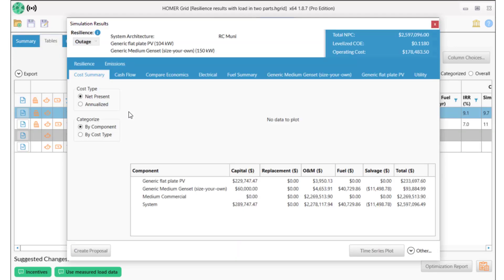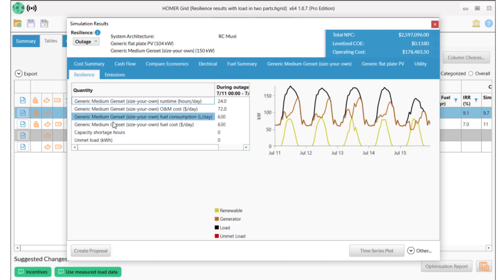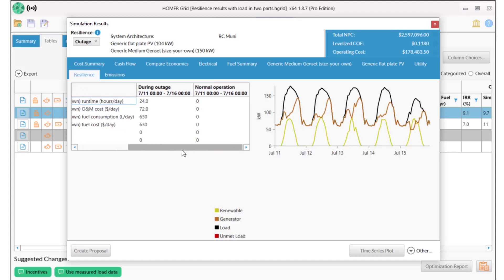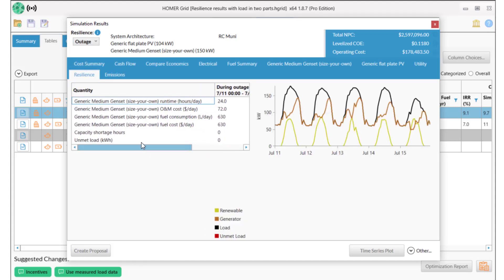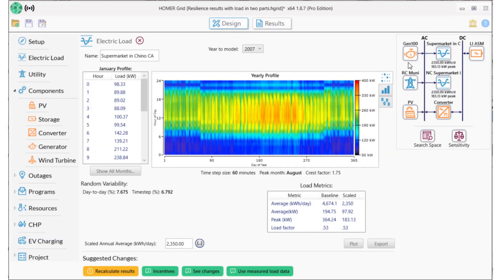Let's look at how the system managed resilience. The generator is running 24 hours per day during the outage, and never during normal operation. The PV is producing midday, as we'd expect. This system requires a big and expensive generator to support this large critical load that only happens 5 days a year.